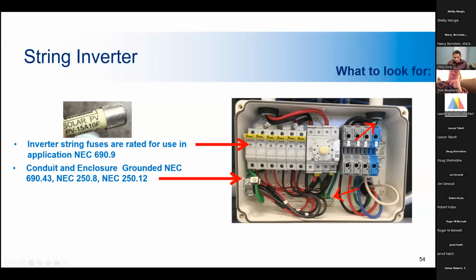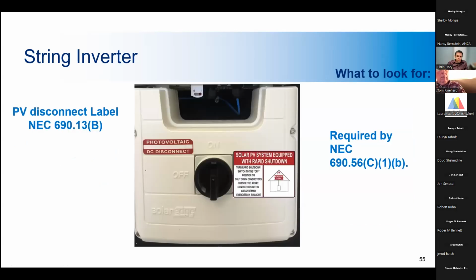You'll also want to check for proper conductor sizing and markings, as well as fusing requirements. Fuses have to be rated specifically for solar PV. You can't just use any DC fuse. And one thing to keep in mind is fuses are supposed to be rated for 600 volts DC for residential or 1000 volts DC for commercial.